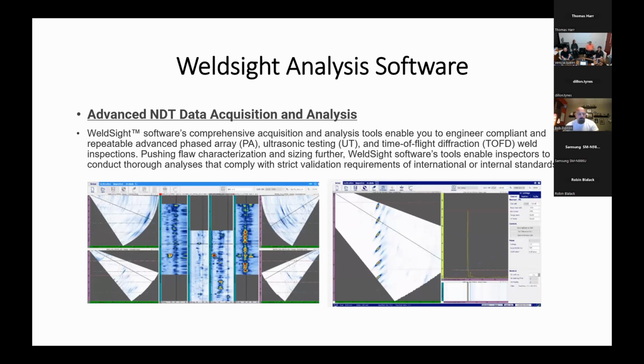So one of the good things that you can compare with the X3, both the 32, 128, and the 64, is what we call WeldSight. It's our analysis software. So WeldSight software's comprehensive acquisition and analysis tools enable you to engineer compliant and repeatable advanced phased array UT and time of flight diffraction weld inspection. Pushing flaw characterization and sizing further, WeldSight software tools enable inspectors to conduct thorough analysis and comply with the strict validation requirements of international or internal standards.